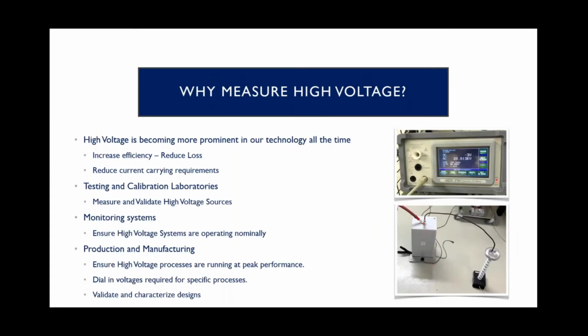So you might ask yourself, why do I need to measure high voltage? Well, high voltage is becoming a lot more prominent in our technology and in our society all the time. Biggest reasons for this is to really increase the efficiency of all of our cabling to reduce loss in long runs. As you get higher current, lower voltage signals, you'll get a lot more loss on your long cabling. It also reduces your current carrying requirements. So with the higher voltage, you can get the same amount of power with much lower currents. So you don't need as much cable as well.